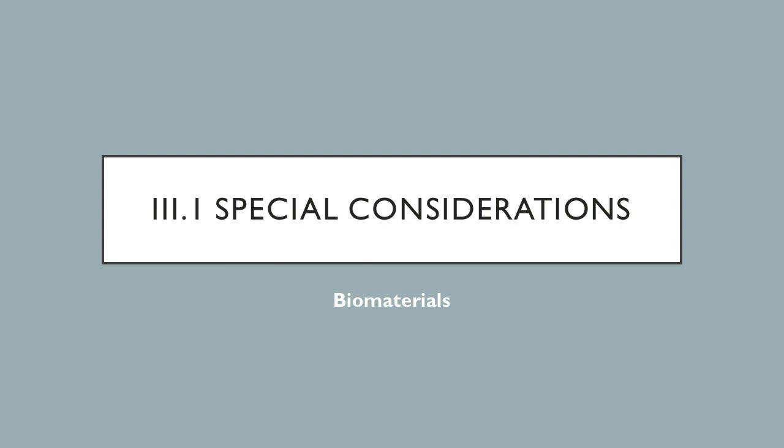This particular chapter in the book, though, discusses some of the special considerations we have to make both during the preclinical stage when we're translating a device from the laboratory to a commercial setting, and then also some of the analysis that we do during a post-market analysis, retrieval studies where we can look at implants and biomaterial devices even after they've been approved, both for the refinement of biomaterials and second generation versions of those devices, but also as a failure analysis that can elucidate some of the failure mechanisms that we wouldn't see in a much more controlled preclinical in vivo setting, and then also during a controlled clinical setting as well. So let's get into it.